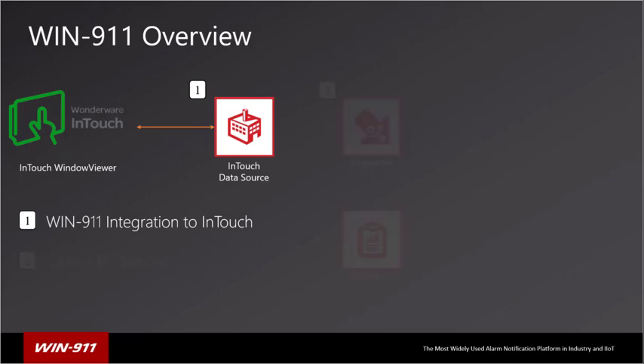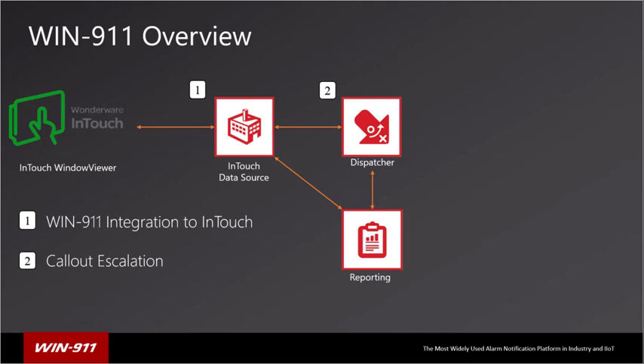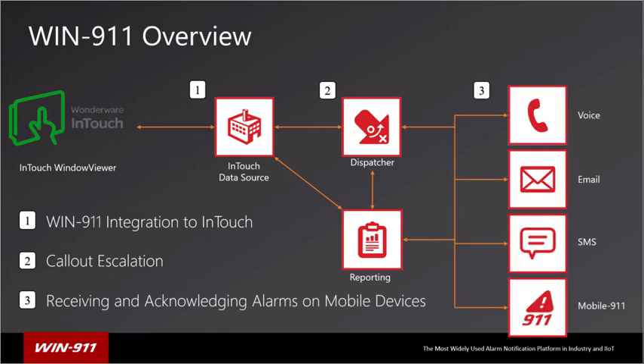After the data source, we send that information on to the dispatcher, as well as the reporting module. The dispatcher is responsible for dispatching those alarms to the appropriate notifier. Notifiers are then responsible for sending those notifications to operators — whichever one you're using: voice, email, SMS, or the mobile app. This is the flow from your SCADA to the data source, to the dispatcher, to the notifiers.